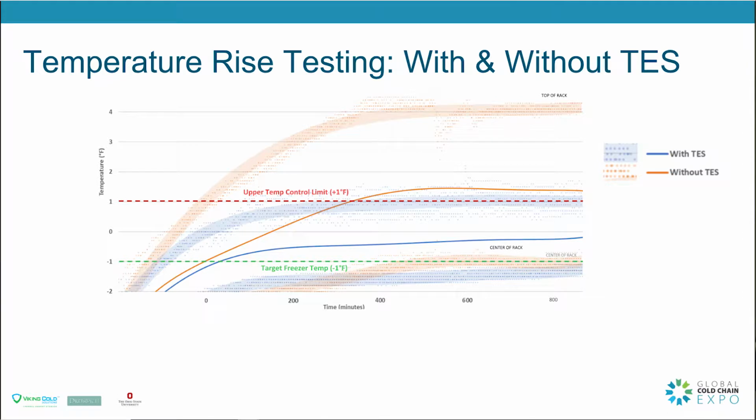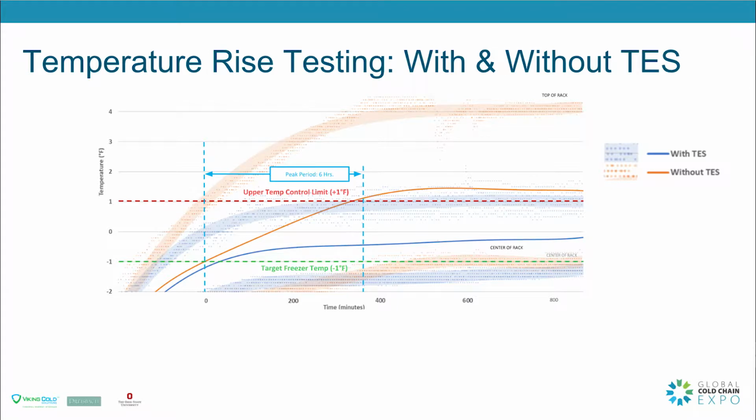And the blue line is post-installation of the average of the top of the room in the center of the racking system. And these, you'd see real little bitty dots. These are hundreds of thousands of data points that we're taking over these periods of time. So as you can see, we started with a 6-hour initial peak period, which was noon to 6 in Jason's territory in PG&E.